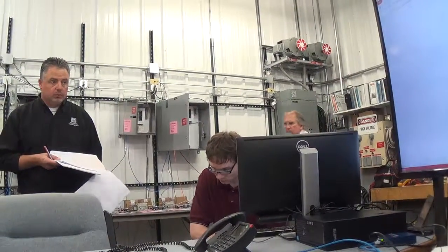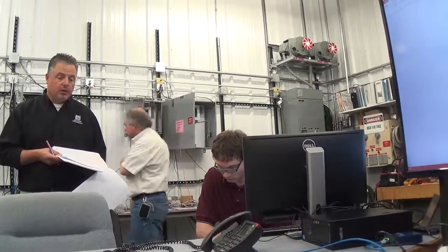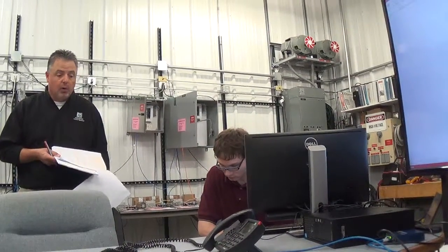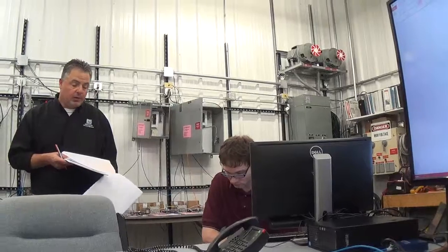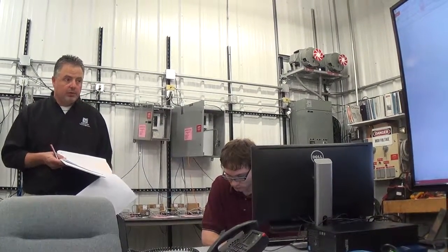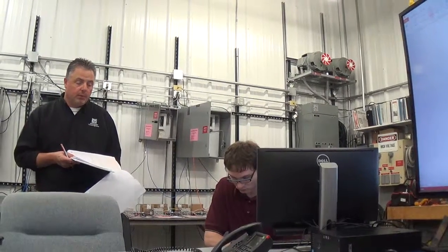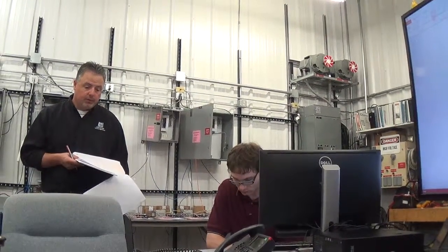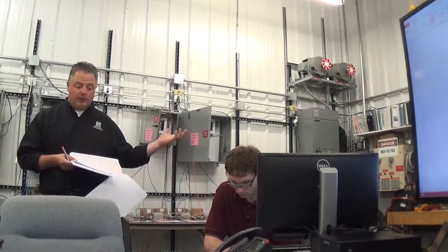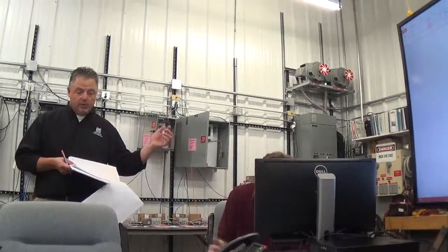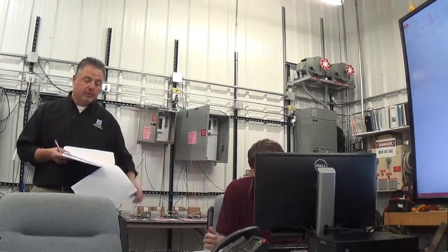Yeah, the flow meter can be set to give us a pulse every 1,000 or every 100 or even every gallon if you want it. I think currently we display it in thousands, but if you need it or want it, we could put a decimal point, so it'd be every 100 gallons. The flow meter does all that. So if it's at 50, when it gets another 50, it gives us a pulse, and we just count up the pulses.